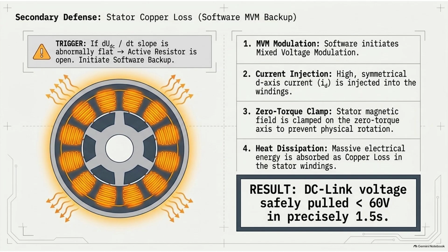Yet the safety system is constantly monitoring the voltage drop in real time. If it triggers the physical discharge resistor and sees that the voltage isn't plummeting fast enough, meaning the resistor must be broken, it abandons that plan and immediately activates the ultimate backup. Which is? Stator copper loss.